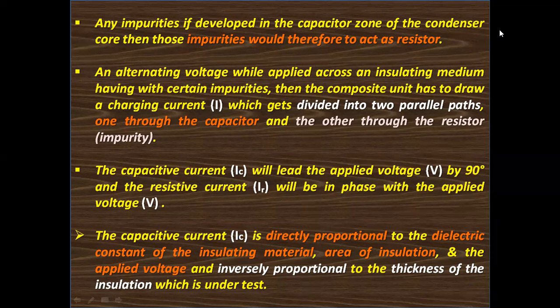And when alternating voltage is applied across an insulating medium having certain impurities, the composite unit draws a charging current I, which gets divided in two parallel paths, one through the capacitor and the other through the resistor, that is the impurity. The capacitive current IC will lead the applied voltage V by 90 degrees, and the resistive current IR will be in phase with the applied voltage V.